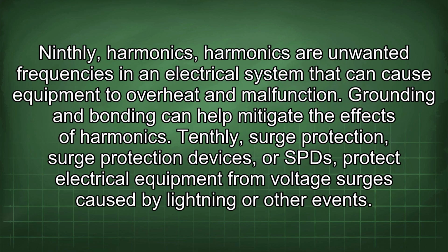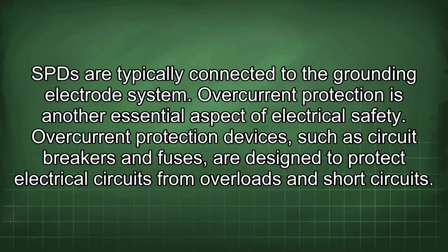Ninthly, harmonics. Harmonics are unwanted frequencies in an electrical system that can cause equipment to overheat and malfunction. Grounding and bonding can help mitigate the effects of harmonics. Tenthly, surge protection. Surge protection devices, or SPDs, protect electrical equipment from voltage surges caused by lightning or other events. SPDs are typically connected to the grounding electrode system.